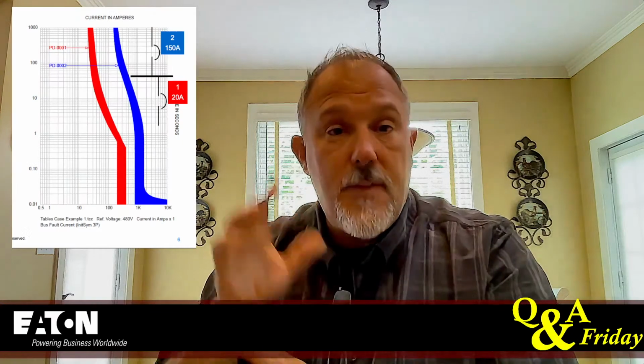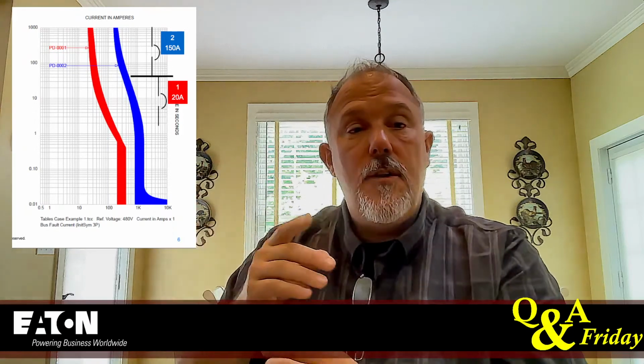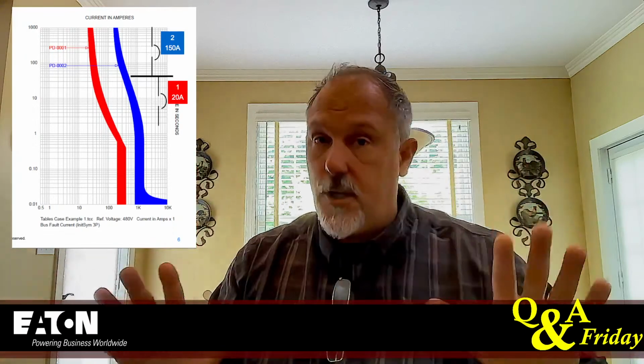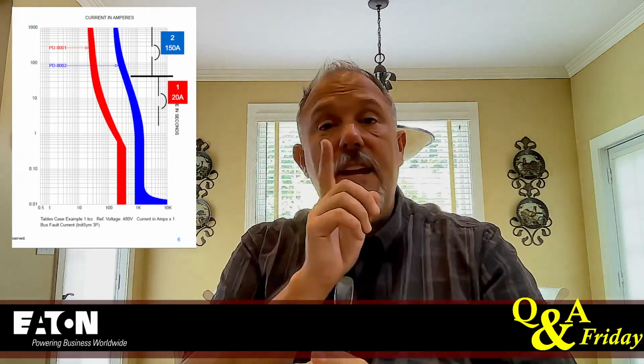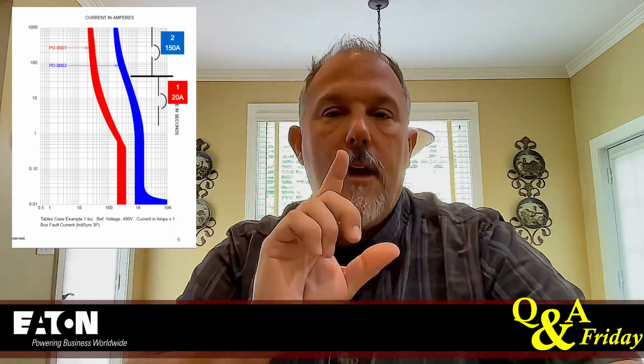Like, for example, on these two curves, imagine, if you will, that these are two air circuit breakers, and let's say that red device doesn't come all the way down. It has just a short time delay. And let's say that the available fault current is less than where the blue curve comes down. I don't need to do anything else. I selectively coordinate. I got separation. I'm good to go. But if the instantaneous is, the instantaneous can overlap, as long as here's what happens.